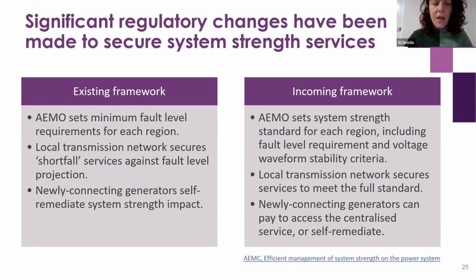We declare those values for the backbone of the network, and the local network goes and delivers. Separately, if a new generator connects to the network, under that 2017 framework they need to bring their own system strength so they don't make the system strength situation worse—they provide their own service or remediate in some way. That's the existing framework, which only came in in 2017.